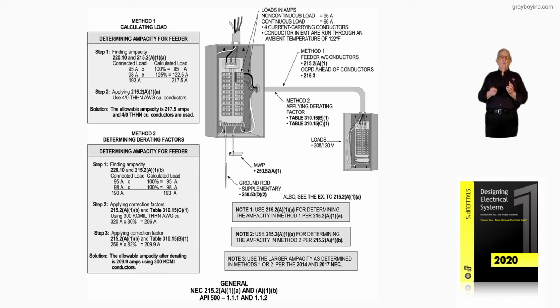So if we load any of those 16 conductors, only 8 of them at one time, we can put them on a 20 amp device and load. But you can only load half of them. And that's what the solution is saying, that we could only load 8 of them at 21 amps. And we would have to have a design so the other 8 could not come in while 8 are being energized and supplying power.